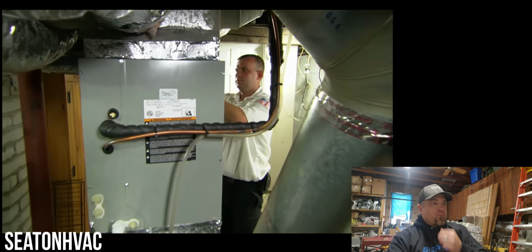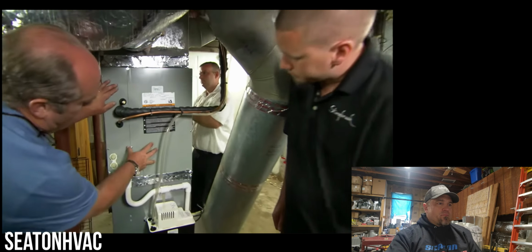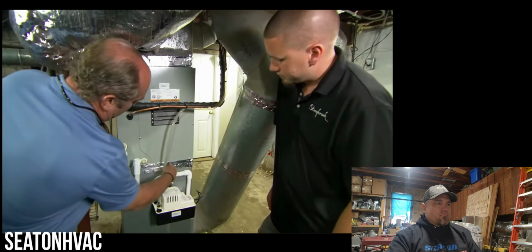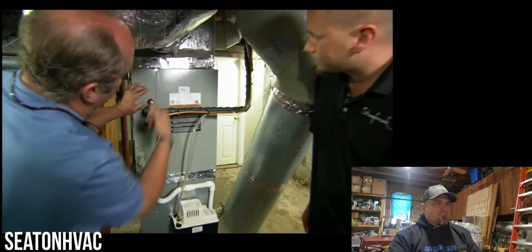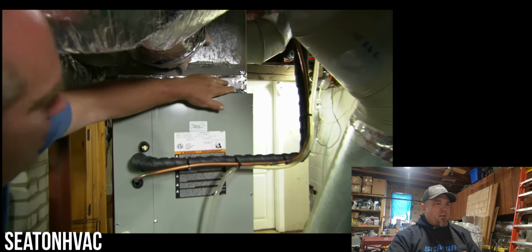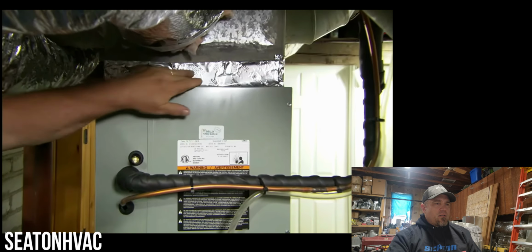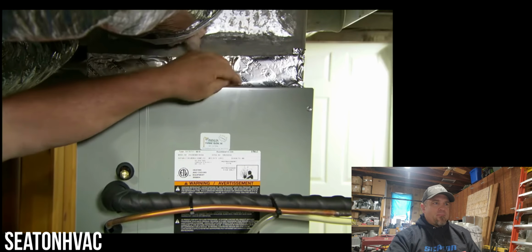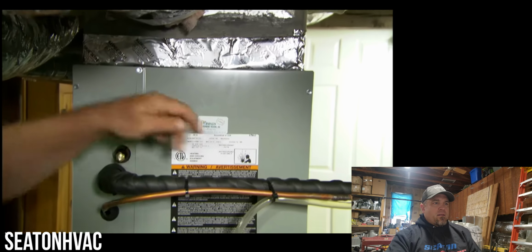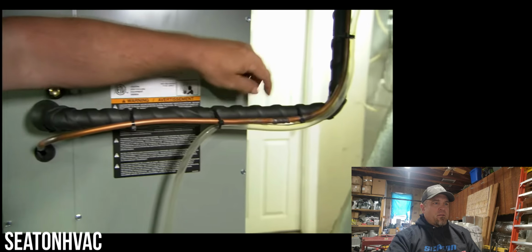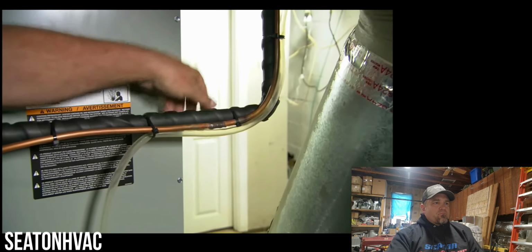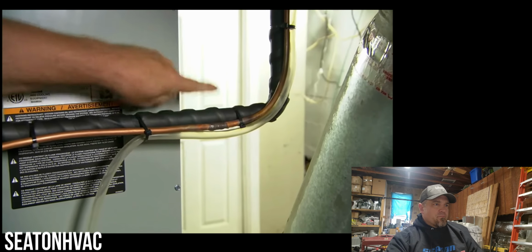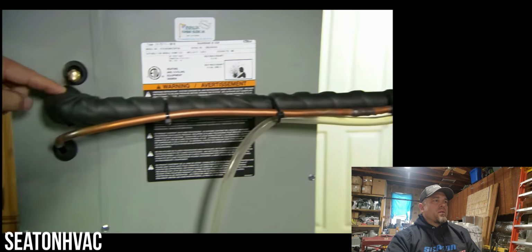So Tim, we've been busy down here. We've got the new coil secured to the furnace with sheet metal screws at the bottom and at the top all the way around. We've sealed it really well with this foil tape with a sealant on the back. We want to make sure there's no air that leaks out into the room. Nice. Okay. Here's the new line sets connected. They've been brazed. And then the suction line, the line that gets colder, has actually been insulated so it doesn't drip anything on the floor.